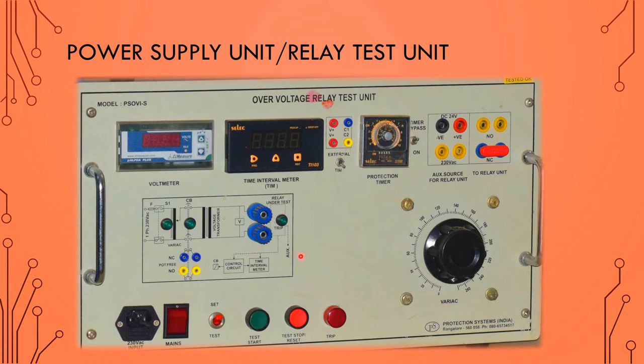So this switch function and the electromechanical switch function are similar. When we press in set mode, we can give the voltage to the relay, but whatever trip signal the relay gives will not come to the circuit breaker. The relay will trip, but that signal will be disconnected by this switch, so the circuit breaker will not sense it, because the signal is bypassed.